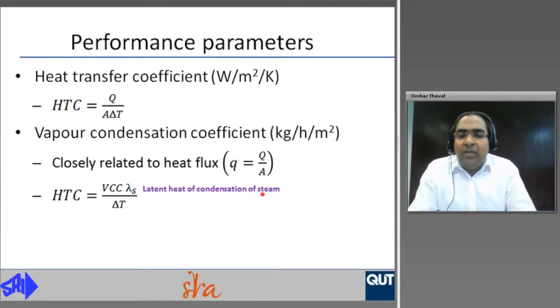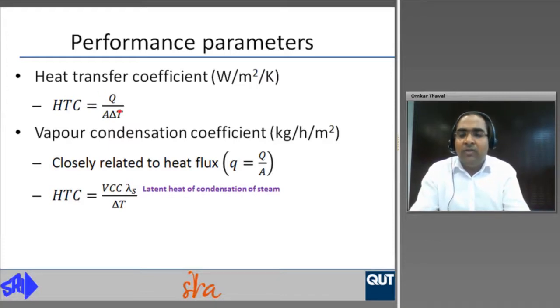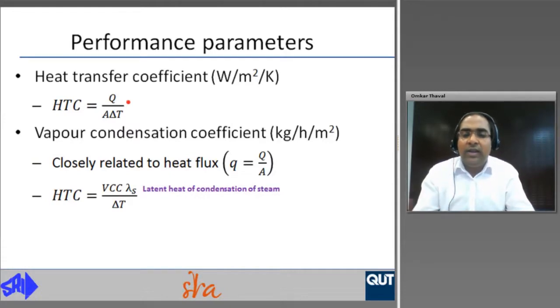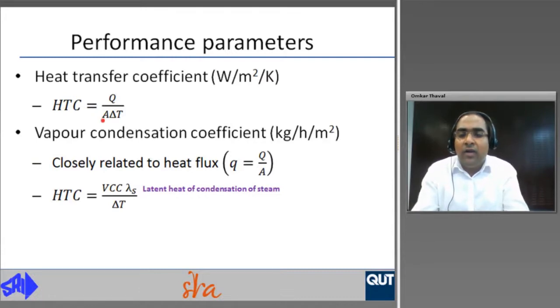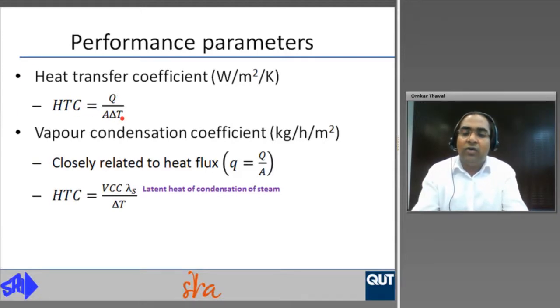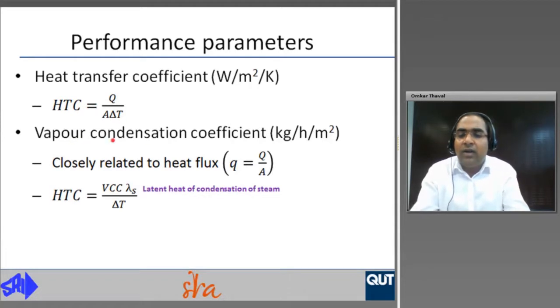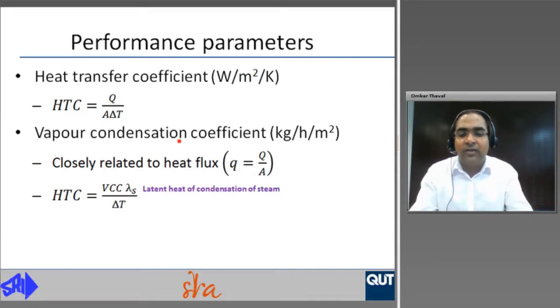The parameters used to define the performance of evaporators are heat transfer coefficient in watts per meter square per Kelvin, given by Q divided by A times delta T, where Q is heat transfer in watts, A is the area in square meters, and delta T is the temperature difference between the heating steam and the juice, also called the driving force for heat transfer. For an evaporator with fixed area and fixed heat transferred, the heat transfer coefficient increases for a smaller delta T. A second parameter is the vapour condensation coefficient (VCC) in kilograms per hour per meter square, which is closely related to heat flux. The relationship between heat transfer coefficient and VCC is given by a corresponding equation.